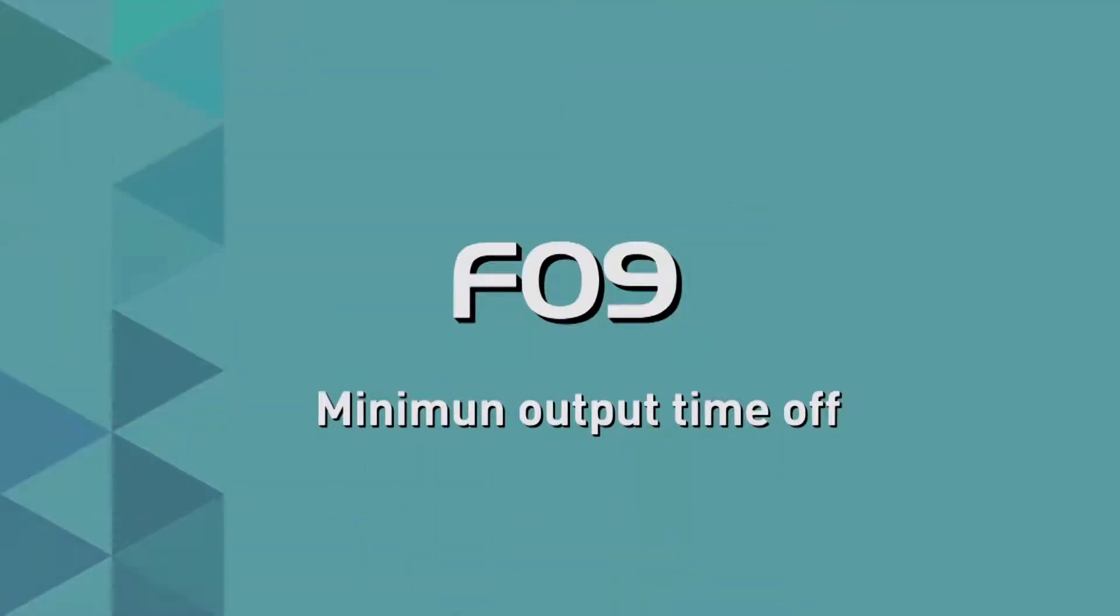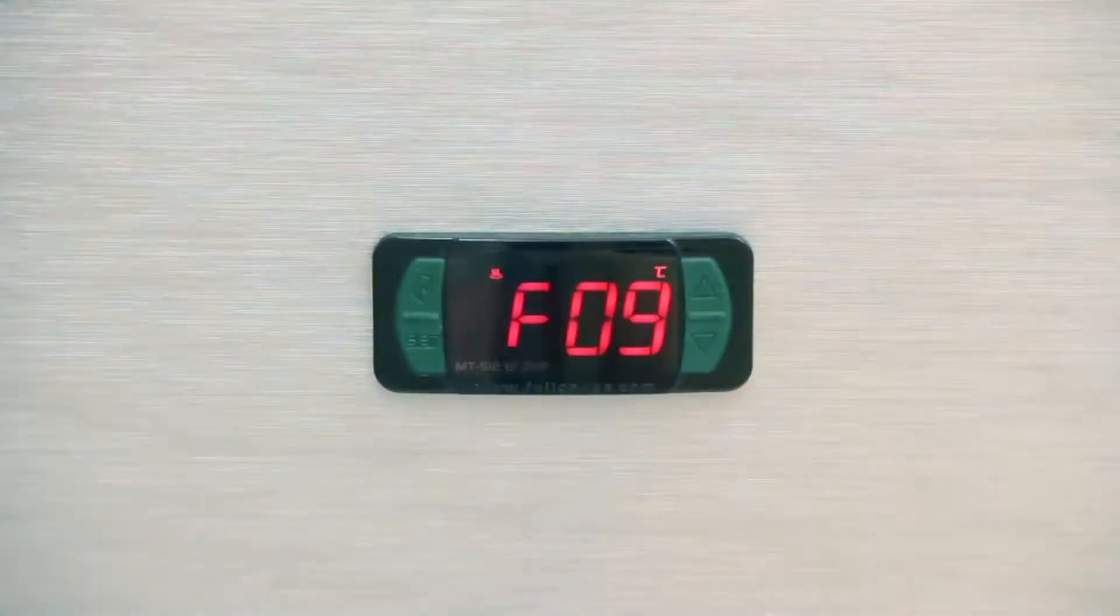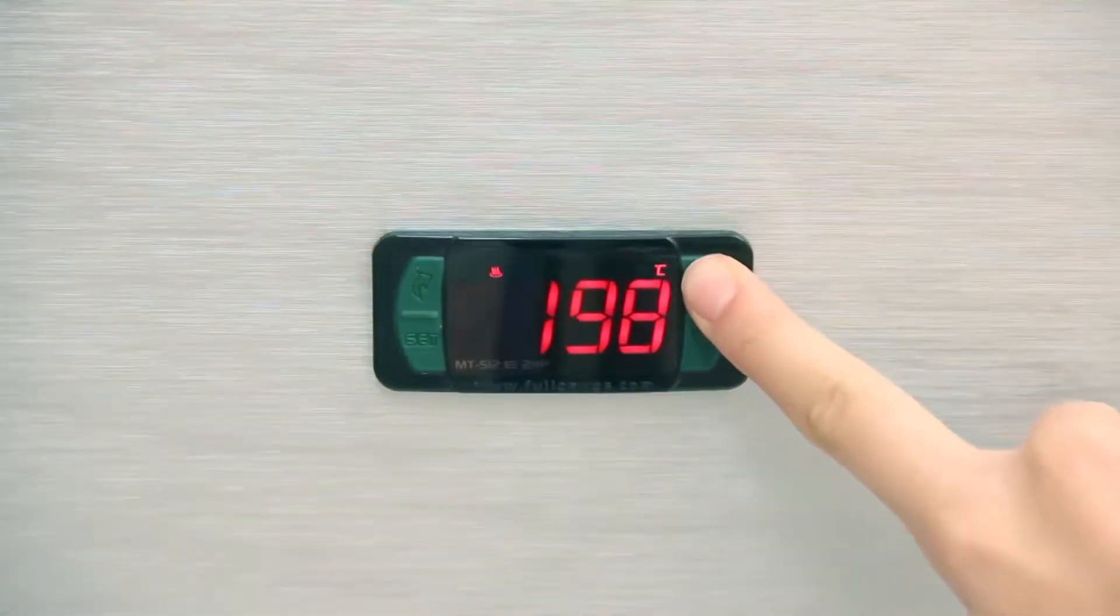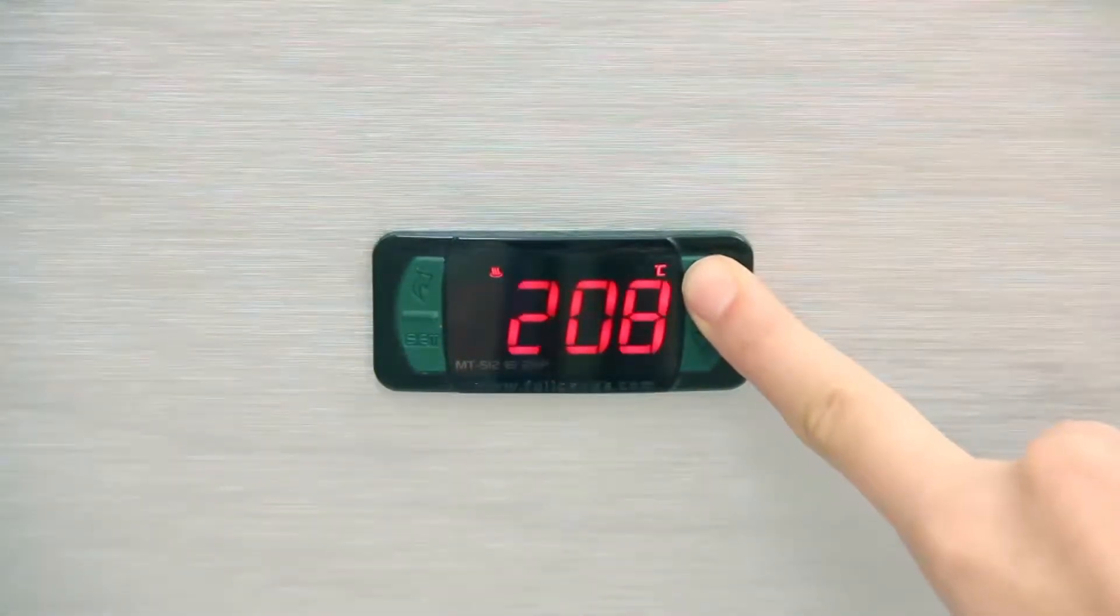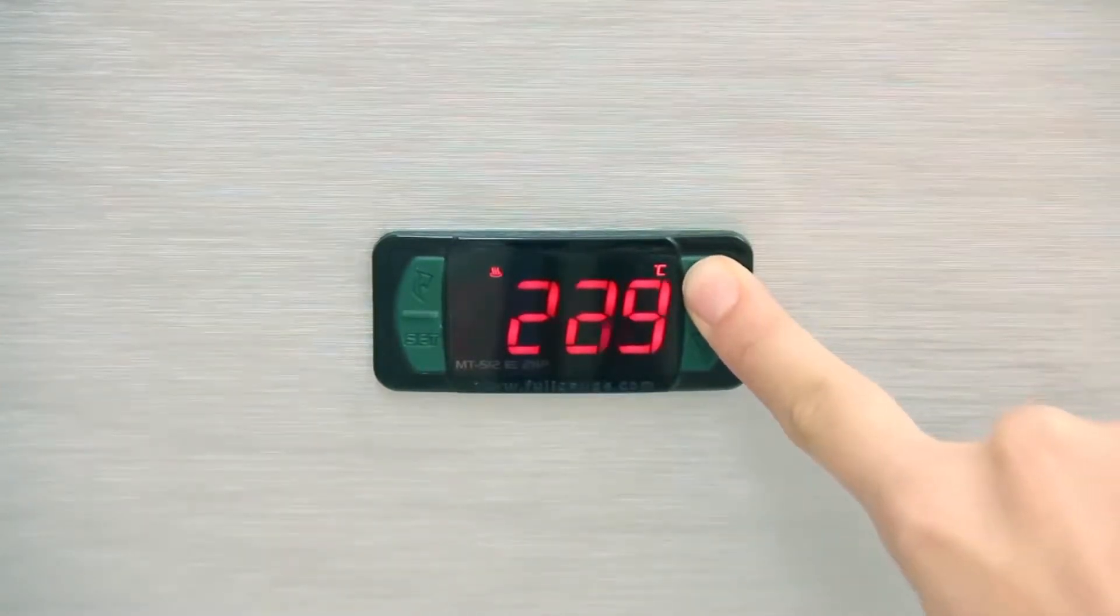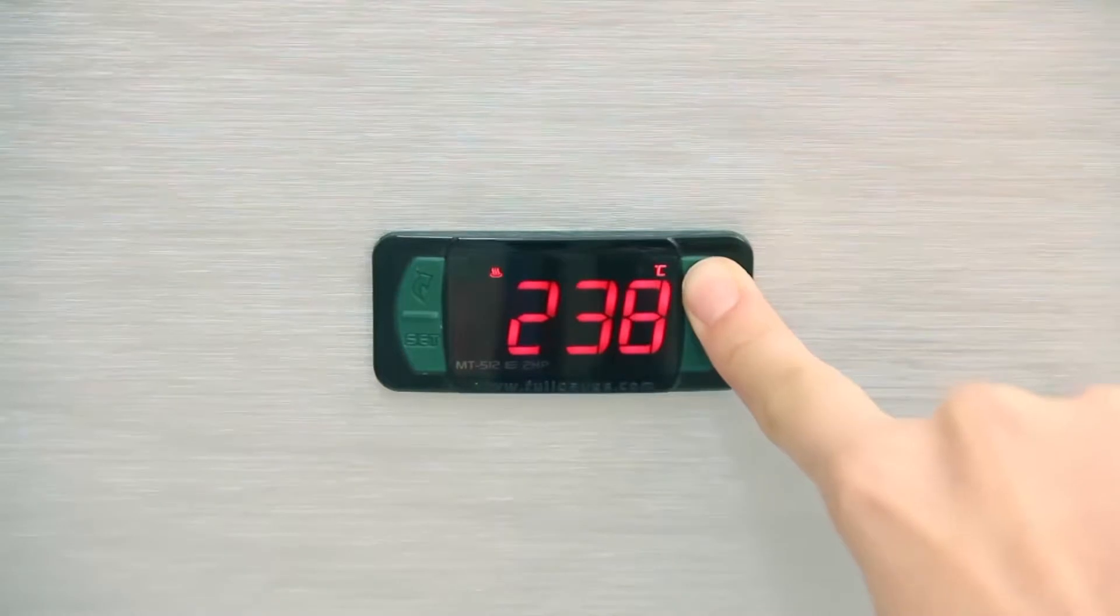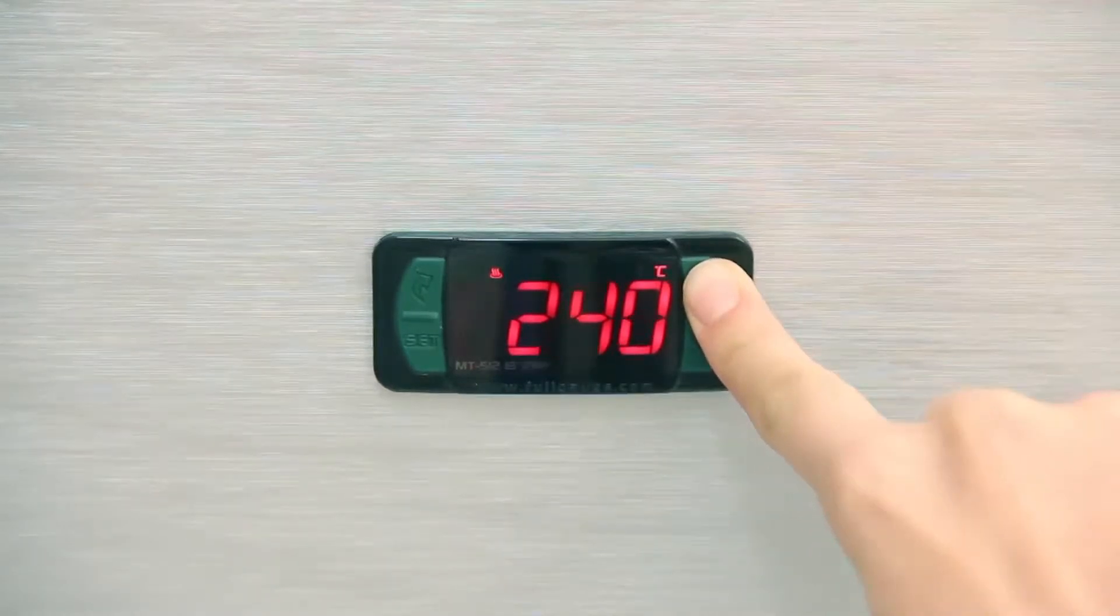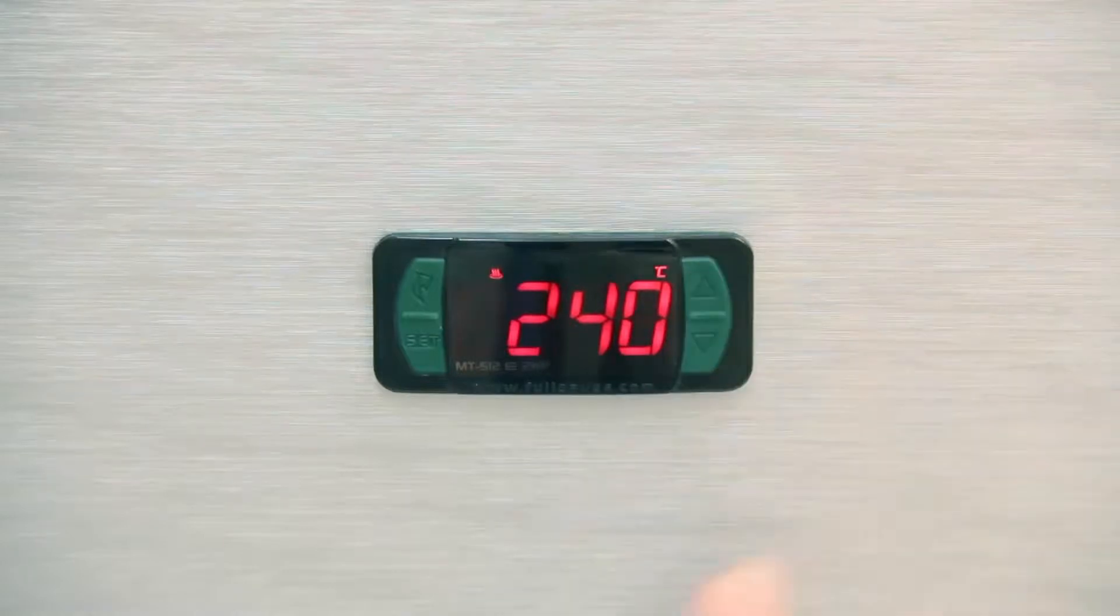F09 Minimum Output Off Time: Similar to the previous parameter, this determines the minimum relay off time since the last start. Select No so as not to adopt a minimum time, or provide a value between 1 and 999 seconds. In the examples, we chose 240 seconds for both applications.